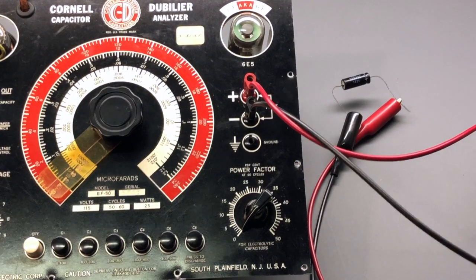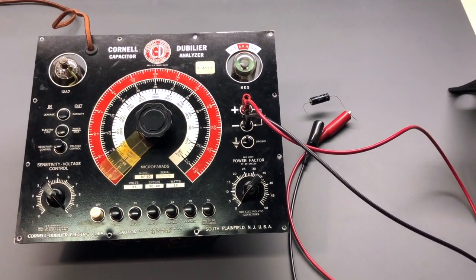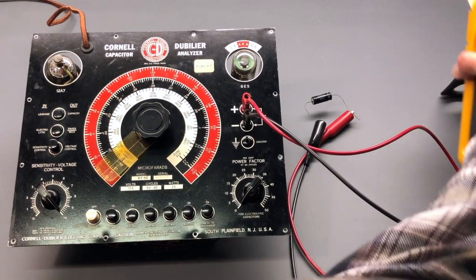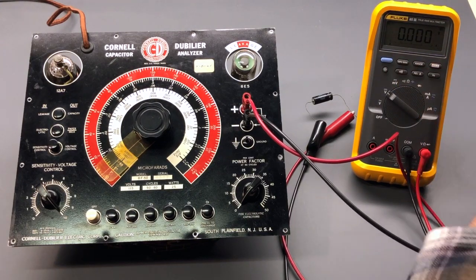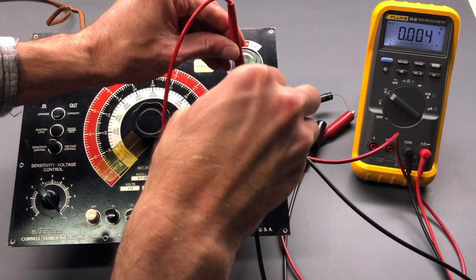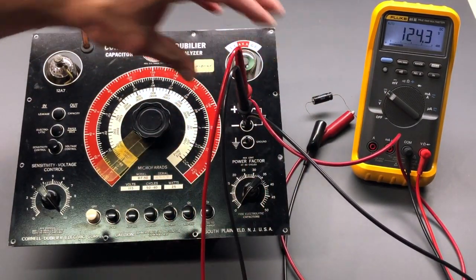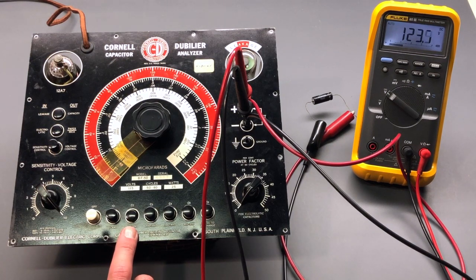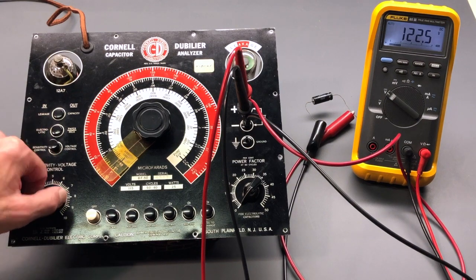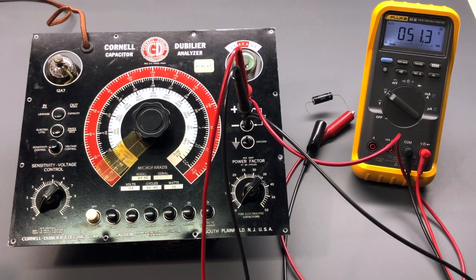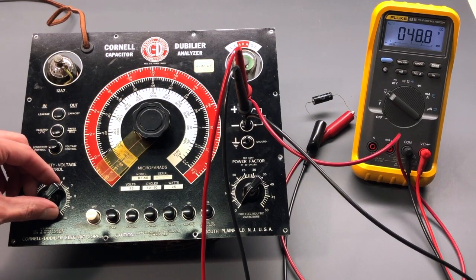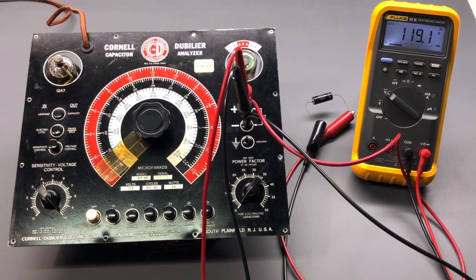So I will take the meter and let me zoom back out here. Let's see what voltage is actually on those test jacks. So right now this is in the 100 to 200 position, and we see 123 volts. If we turn this down, it really does fall away quite a bit, down to 50. Turning this back up, it slowly increases. So that capacitor does look like it changes those values, where before with nothing connected this came up to 200 volts when this was at the 10 position over here.